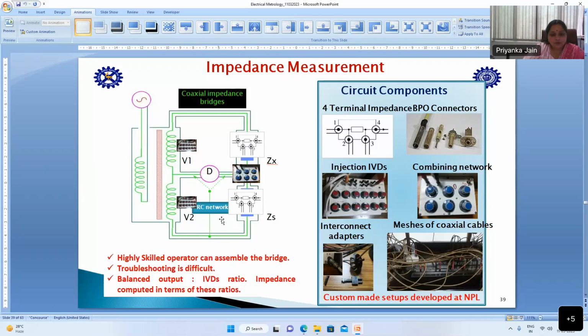Along with these, you have to balance the bridge for these parasitic compensation. So you have an RC network for phase shifting, because if you want to balance the in-phase component, in phase means in the direction of your applied voltage. If you want to balance the in-phase voltage, you have to apply some phase to the circuit. So this phase can be applied to the divider side, or the voltage supply side, or in the DUT side.